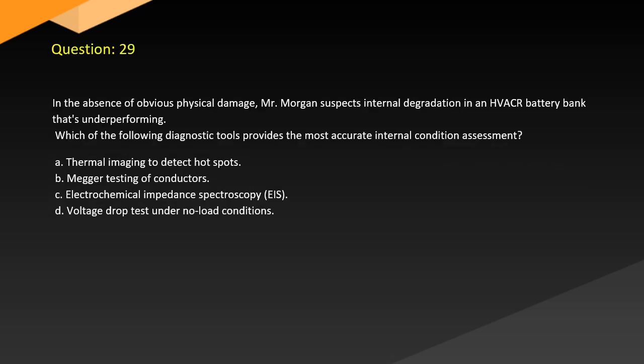Question 29. In the absence of obvious physical damage, Mr. Morgan suspects internal degradation in an HVACR battery bank that's underperforming. Which of the following diagnostic tools provides the most accurate internal condition assessment? A. Thermal imaging to detect hotspots. B. Megger testing of conductors. C. Electrochemical impedance spectroscopy, EIS. D. Voltage drop test under no-load conditions.